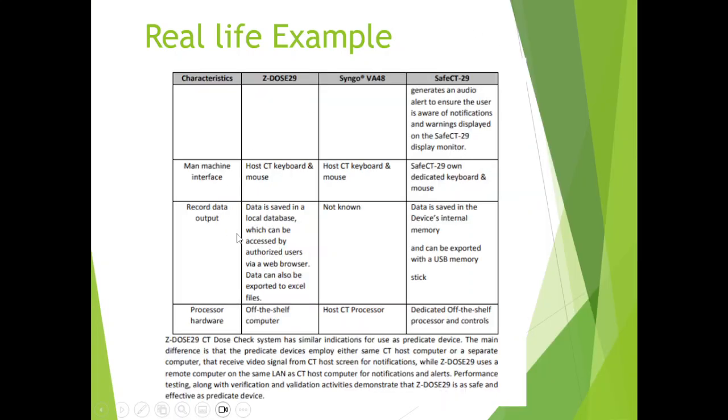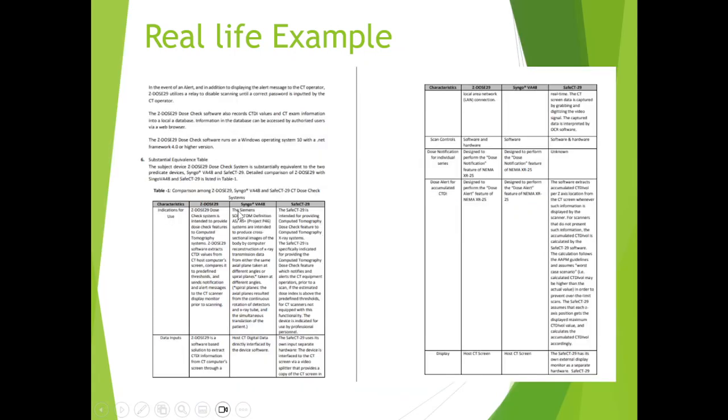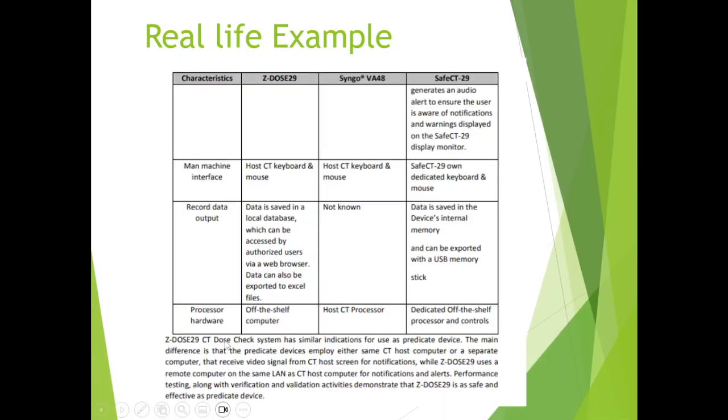And here is the continuation of the same table. We actually took the characteristics of the data input and scan controls, starting from this predicate device, which also cited all these characteristics, and we try to demonstrate our similarities and differences. And lastly, we will have a summary, saying it has similar indications for use.